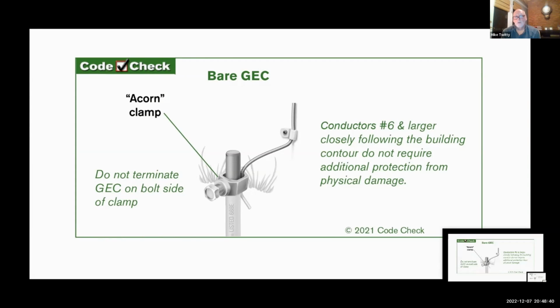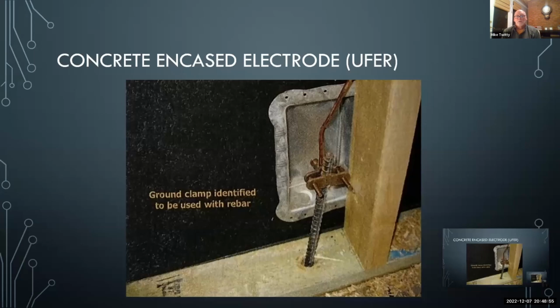And that's a lot cheaper than going through the test. If you drive that second rod, you don't have to prove anything. They don't do any tests. It may still not be less than 25 ohms, but they don't check it. That's just a provision that's allowed for 2 rods. Going back to the UFER, that can be the sole electrode. It doesn't require a supplemental rod per code.